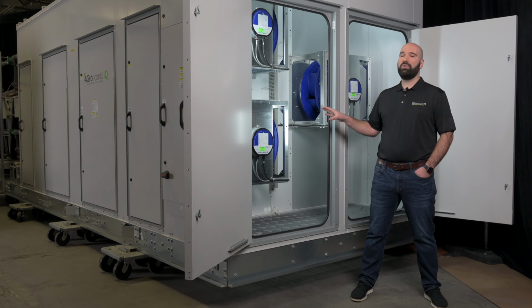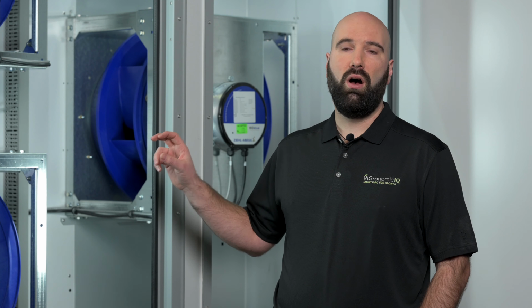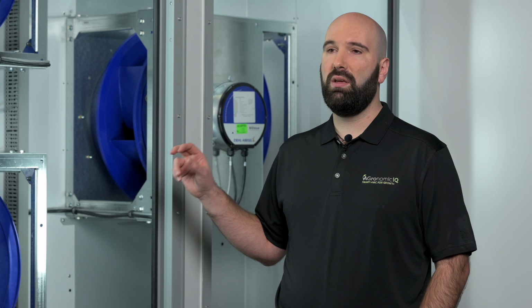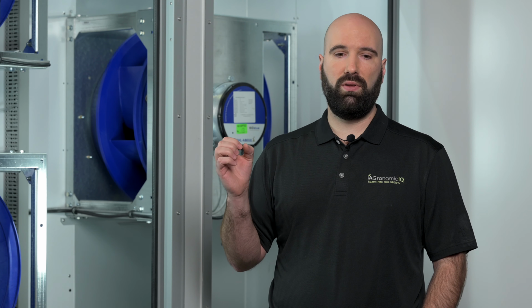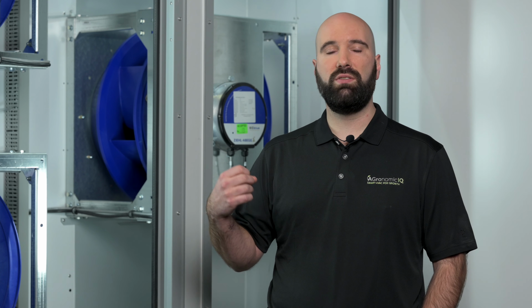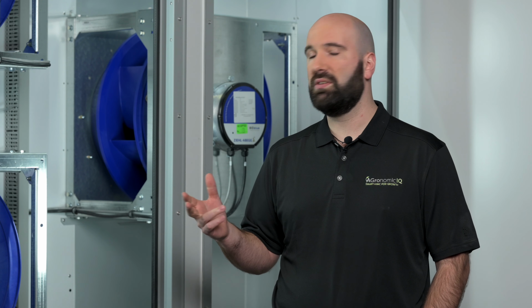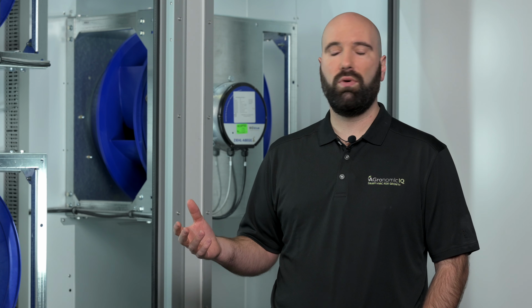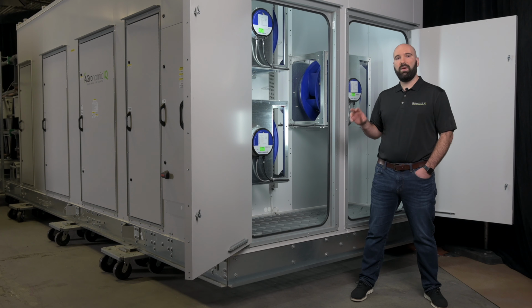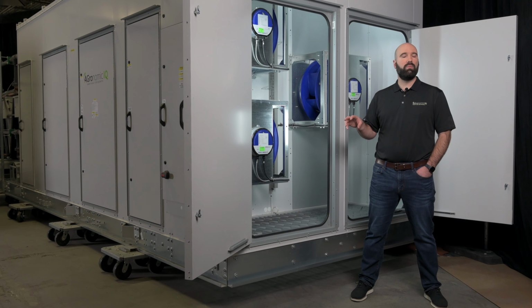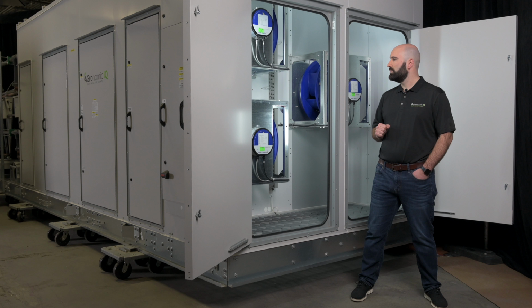And each fan is also equipped with airflow monitoring on these fan wall units, meaning that you can set an airflow value and the unit will turn up or down the fans based on filter loading or based on coil wetting or any of a half dozen other things that would affect your overall airflow. That allows you to get very consistent airflow through your space, a very consistent environment in your space, ensuring that there's no stratification or any of the other sort of typical temperature problems that you'd find.